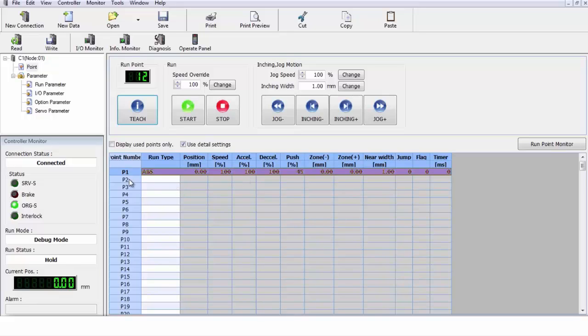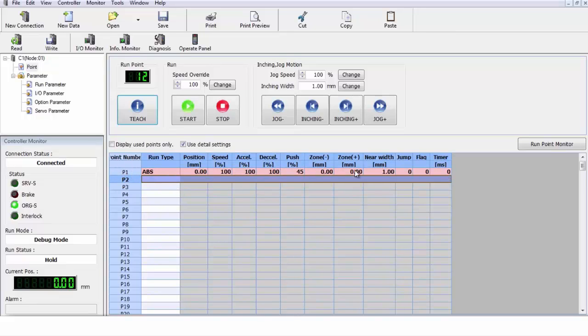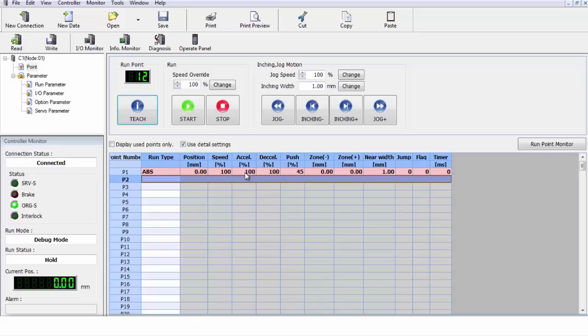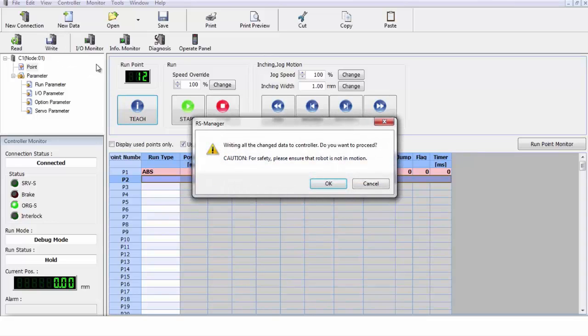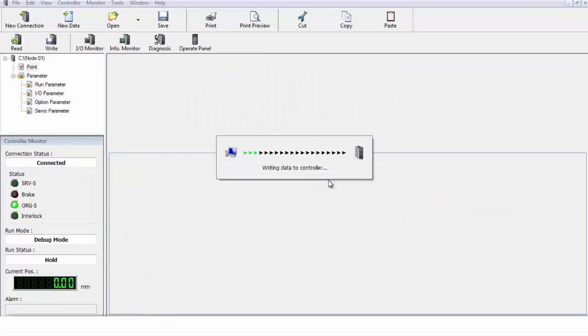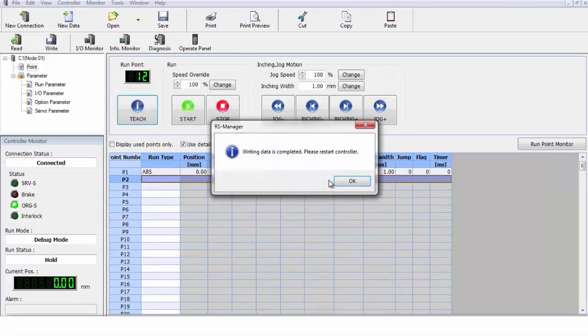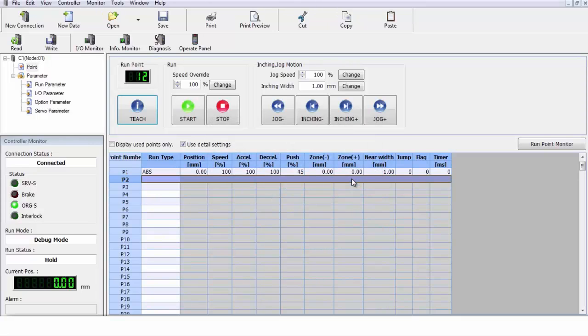I'm going to go back over here and I'm going to add a few more moves in. Now you'll notice here we put one of these moves in that everything is highlighted. This means that the program that's on the screen is different than the one that's in the controller. So if we want to save this down to the controller we go up and we write it to the controller. You'll get a warning here that you're about to write software to the controller. You click on OK. It writes the data down to the controller. As soon as the data has been written you get an OK back and you'll notice that the program line is no longer highlighted. So the information that's on the screen matches what's in the controller.